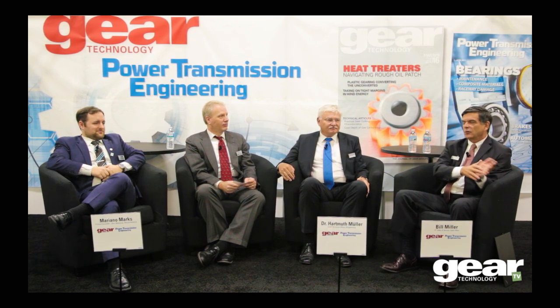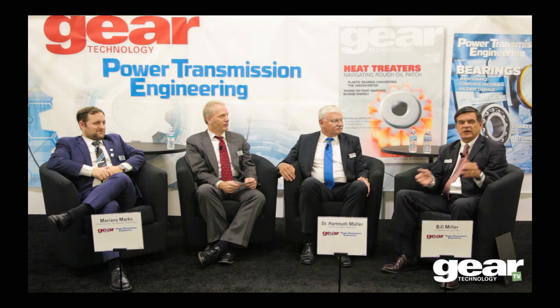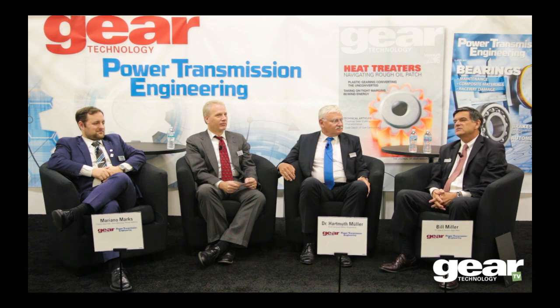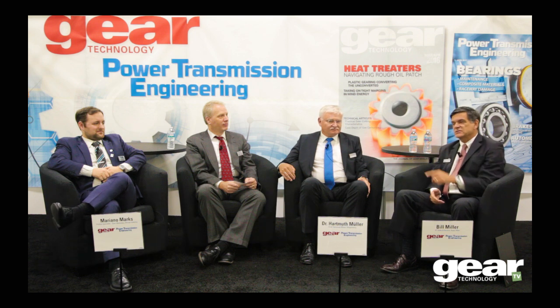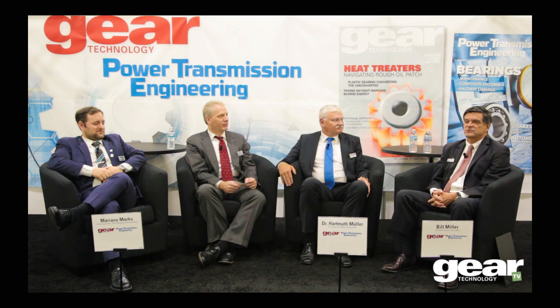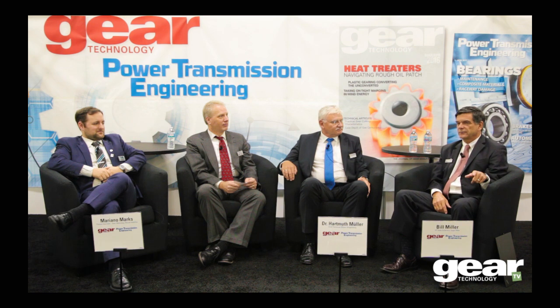Nevertheless, they will come. I have a rule, and I advise everyone: if you get a report from the lab and there's a red mark that it's out of tolerance, so many manufacturing people run out to the maintenance department or run to their supervisor or run to the engineer and say, what do I do? They shut down the machine. And I say, turn around and go back to the lab and tell that guy to measure it again, and then ask him to calibrate it for you. And stand there and watch him. The guy running the grinding machine, which is a $1 million machine, is the boss. Take control.